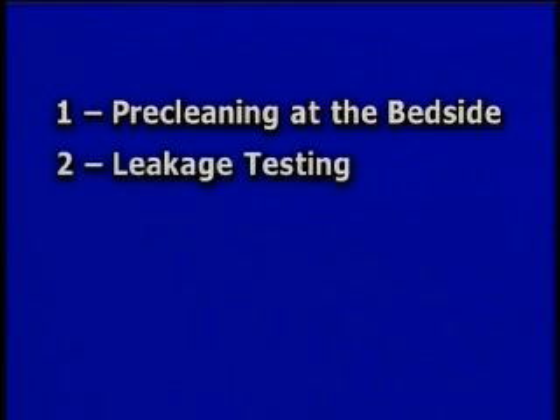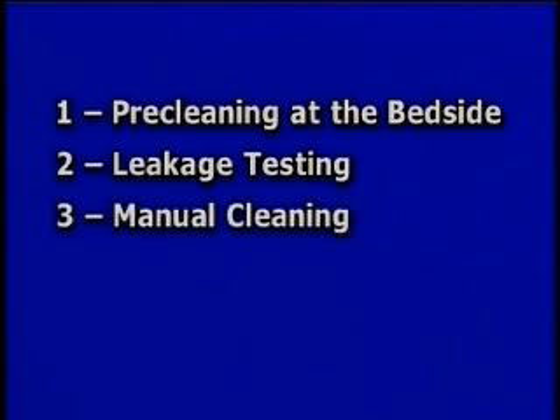2. Leakage testing is required to ensure that the channels and insertion tube are not damaged and that all seals are air and watertight. Routine leakage testing prevents costly fluid invasion and therefore high-cost instrument repairs. Never use an endoscope that has a known leak on a patient. 3. A critical step is meticulous manual cleaning with a detergent or enzymatic solution. Use appropriate brushes and cloths to thoroughly clean all exterior surfaces and internal lumens.